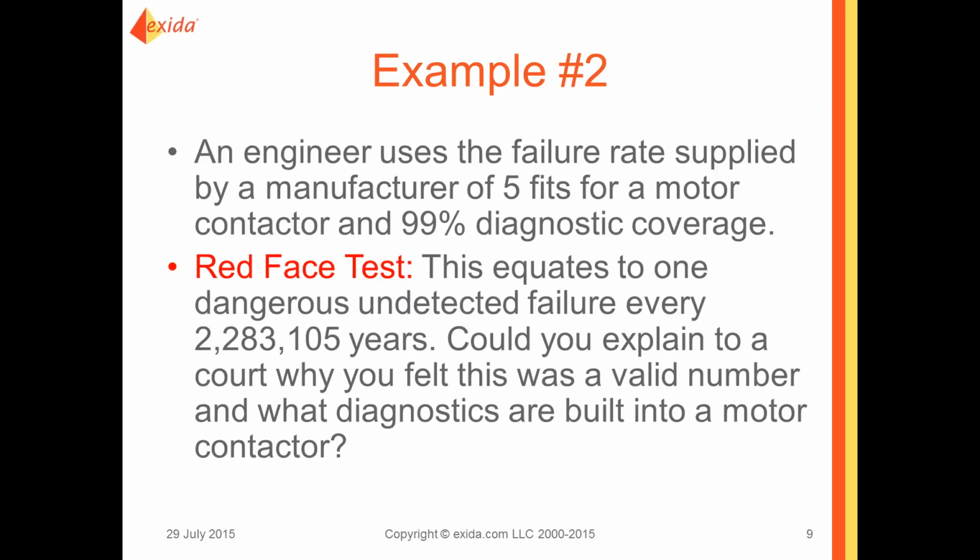So unless they were frequently, daily, de-energizing and re-energizing that contactor, there would be no way to know if the dominant failure mode, which would be welding of contacts for dangerous, occurred. So the number, as we can see, of 2.2 million years is unrealistic, and so is the concept of an automatic diagnostic. In 61508, a diagnostic is an automatic test that's performed to detect a dangerous failure and enunciate it.